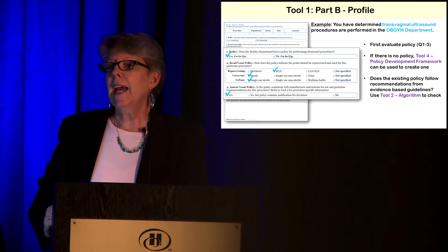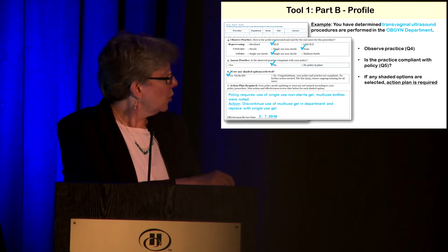All right, this is the second half of this tool. This takes you through the practice observation. So how is the ultrasound probe handled in real life? In this example, you'll recall the policy calls for high-level disinfection, a sterile sheath, and sterile gel. In practice, however, high-level disinfection is used. However, no cover and non-sterile gel was used. Therefore, number 5 is marked as no. And if there are any shaded areas on this page, you will develop an action plan with your partners in the place where they're using ultrasound. And in this example, it does show the beginning of an action plan.